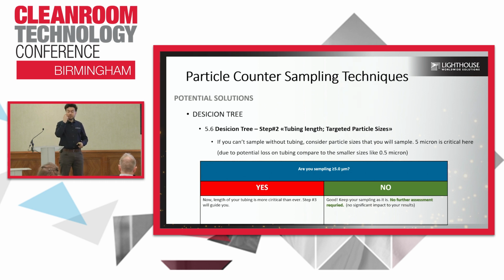The reason here is important. Don't forget, all the ISO 14644 standards are for all industries. We know we are trying to capture the pharmaceutical requirement for 5 micron here a little bit, but for the rest, you still have your own risk assessment, which means the technical report doesn't give you the full aspect of your industry. For example, we said no further assessment required when you sample not 5 micron, but the rest is also applicable to, for example, the automotive industry, because in an automotive paint shop, we have longer distance tubing where we do the sampling for 5 micron, 0.3 micron, and 0.5 micron particle sizes. If this is the case, then the tube length will not be critical, because these are ISO class 8 cleanrooms, where you are sampling millions of particles. So losing a couple of them within the tubing will not really affect you. But maybe in your application, even if you are not sampling 5 micron, you will have a risk. That's why you have to look at it based on your industry needs.